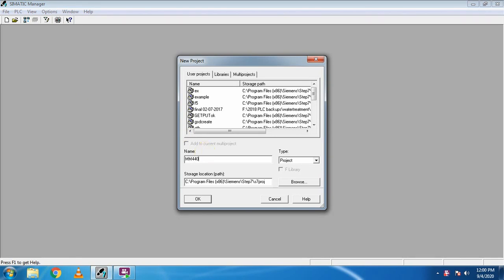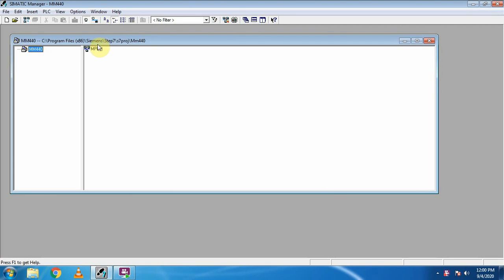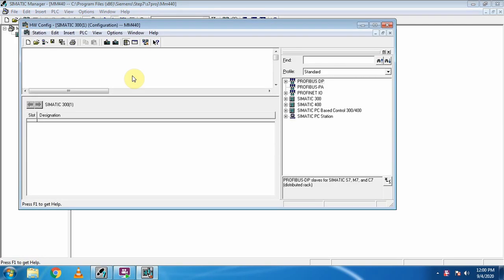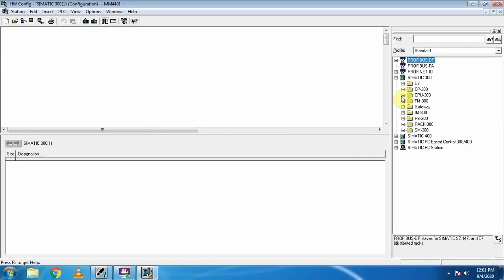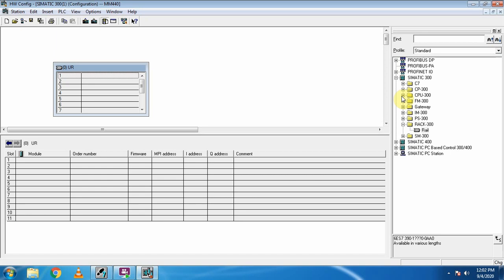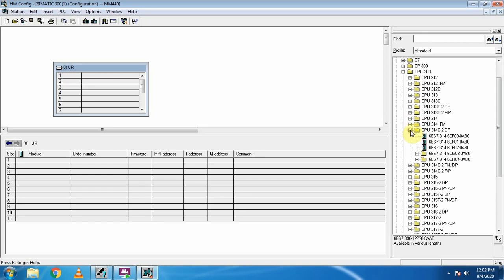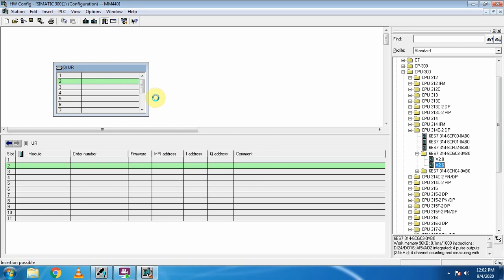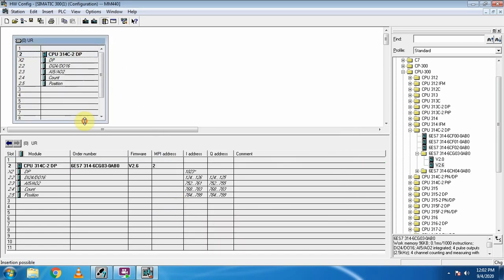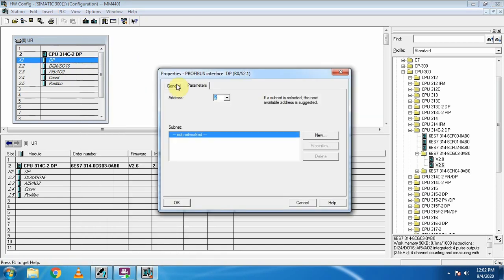Now we will open our Simatic Manager, make our project, and go to the hardware configuration. Here we will insert one S7300 station. First we have to insert the rail, and after inserting the rail we select our CPU. Today we are using the S7-300 2DP PLC — we drag and drop it onto the rail. There is no need to do any additional settings; just press OK, then right-click on the DP and add master system.